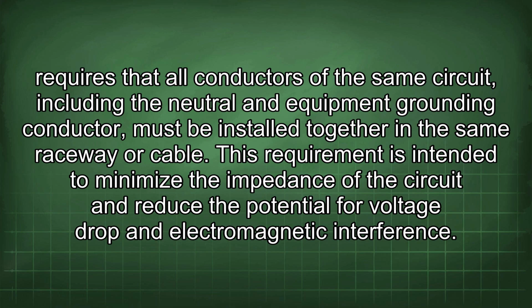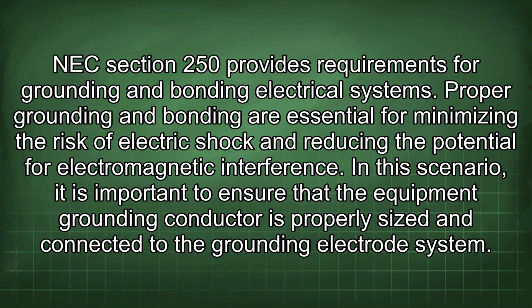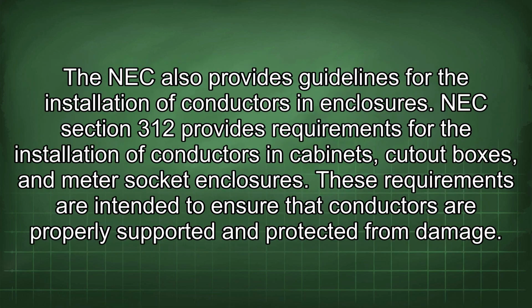This requirement is intended to minimize the impedance of the circuit and reduce the potential for voltage drop and electromagnetic interference. NEC Section 250 provides requirements for grounding and bonding electrical systems. Proper grounding and bonding are essential for minimizing the risk of electric shock and reducing the potential for electromagnetic interference. In this scenario, it is important to ensure that the equipment grounding conductor is properly sized and connected to the grounding electrode system. The NEC also provides guidelines for the installation of conductors in enclosures.